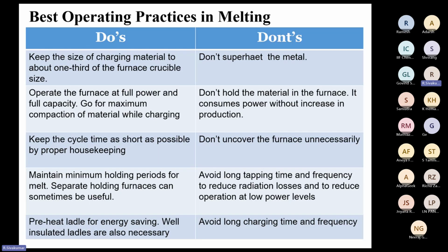Always keep the size of the charging material at 1/3 of the furnace crucible size. This is always instructed by the furnace manufacturer, like Inductotherm or Electrotherm. Your chargeable material length and breadth should be 1/3 of the furnace crucible size, and do not superheat the metal. Operate the furnace at full power and full capacity. Go for maximum compaction of material while charging, and don't hold the material in the furnace, as it consumes power without increasing production. Keep the cycle time as short as possible by proper housekeeping.